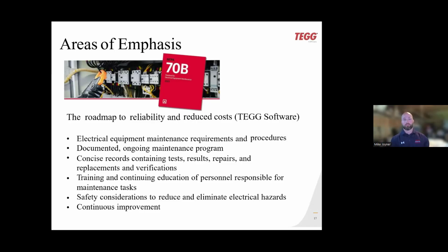Because of the new code, table 9.2.2 states all electrical equipment has to be infrared scanned every 12 months. So in doing so, we now do 3-year contracts with all infrared scanning, but we also offer a separate de-energized maintenance contract. With that, we still incorporate the same scenario, where any problems we find, we try to take care of during the de-energized maintenance and go from there.